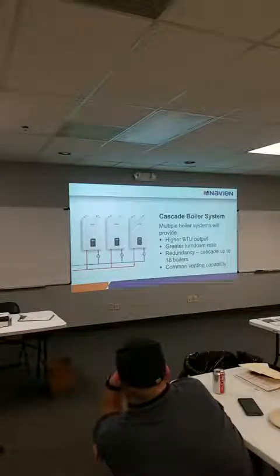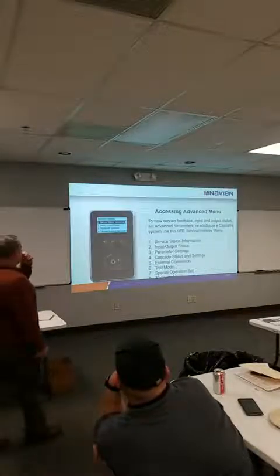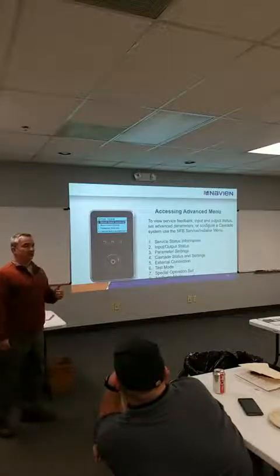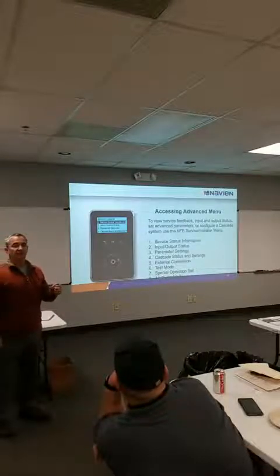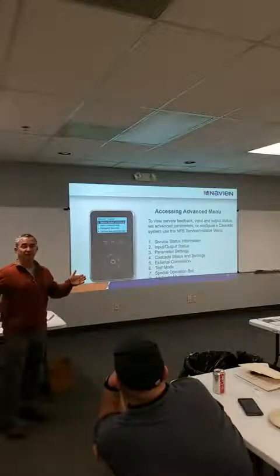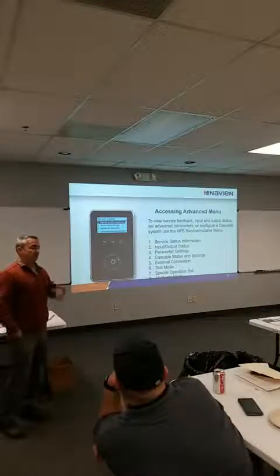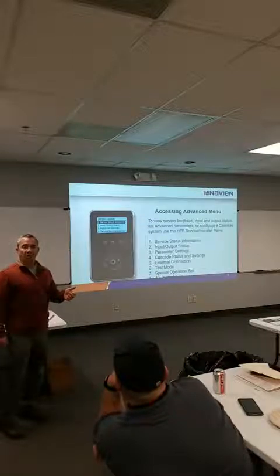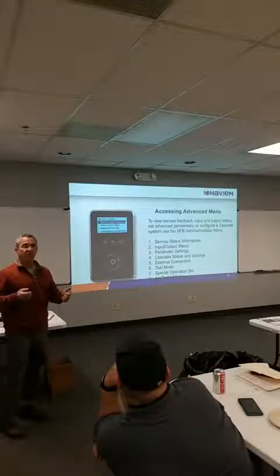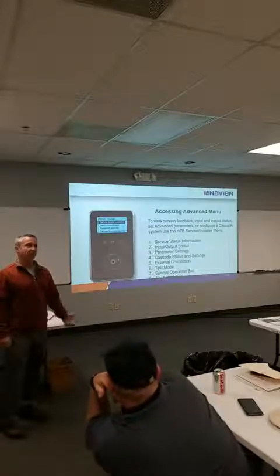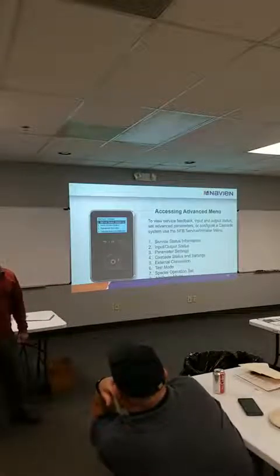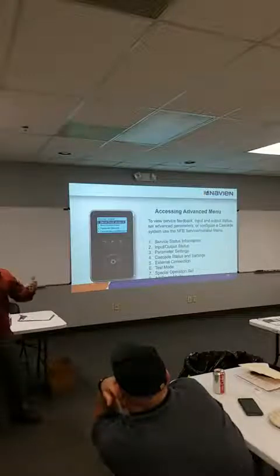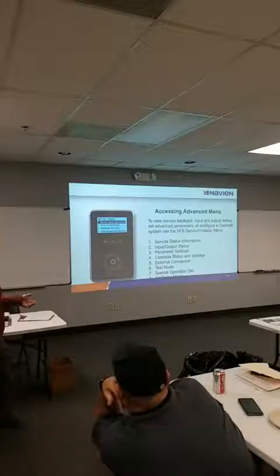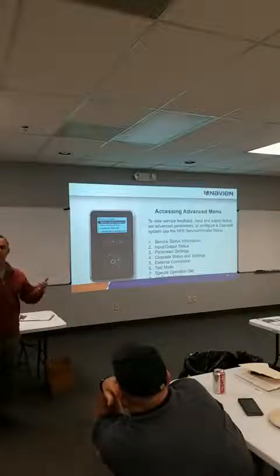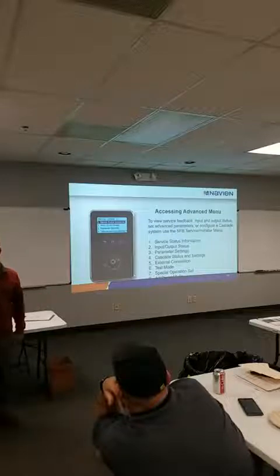What does that air purge mode do? If anybody's put in any of the original combis, when you first turn that thing on, it'll turn itself on once you put power to it. It basically goes into an auto air purge mode, rolling the pump and trying to get the air out of the heat exchanger. It'll run for anywhere from 10 to 20 minutes, usually, but basically it's trying to clear itself. On the combi, since it's got a built-in autofill valve, it's actually autofilling the system and purging the air out on its own.